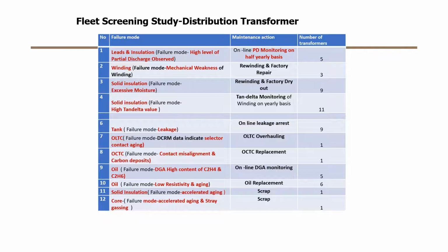No, it's not about only the transformer. It's about all the system, all the equipment you have in your system. So this is winding, solid insulation, excessive moisture. If you have moisture in your insulation, either it has come wet from the factory itself, there is no proper dry out at the factory, or at the site it got some exposure during commissioning, or you have excessive leakage in the tank and you have moisture, then the life of the transformer will be very short. You don't expect 40 years or 30 years, you expect 15 years. After 15 years, your DP value of the transformer is going to be very down. So don't allow any transformer which is wet to be in your system.